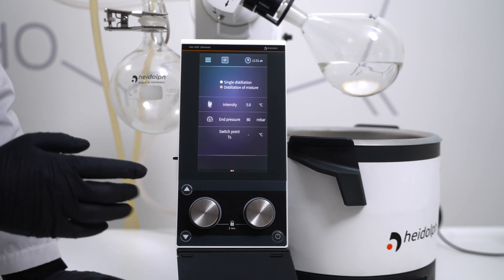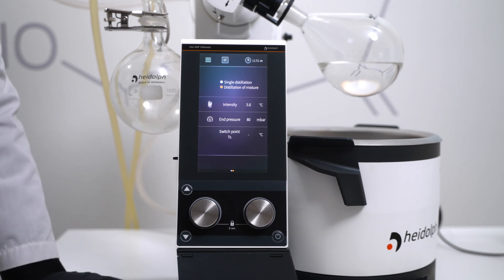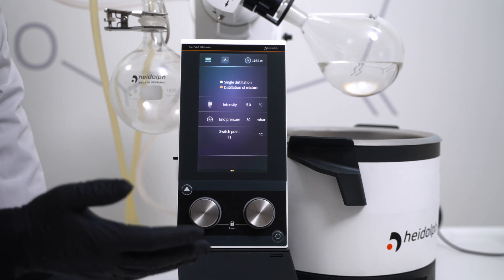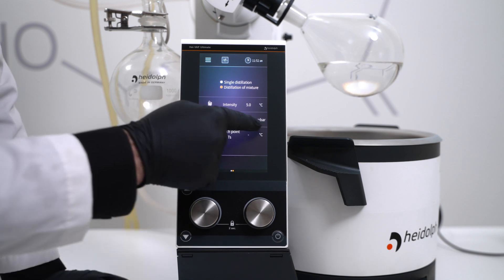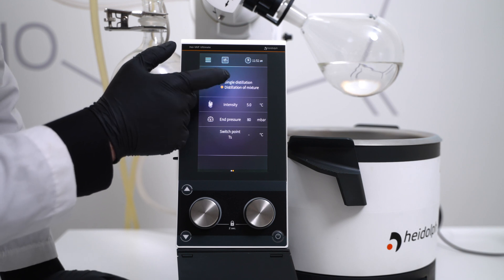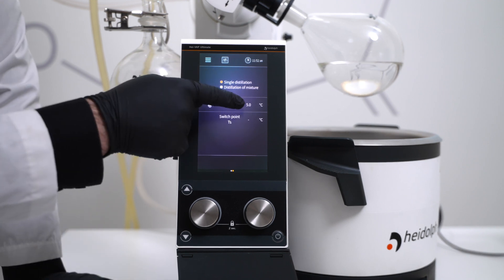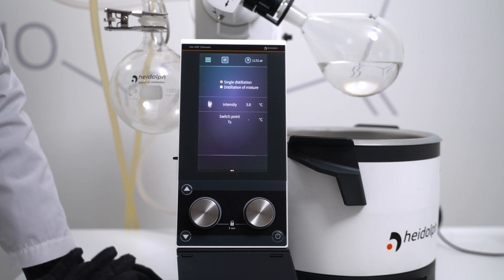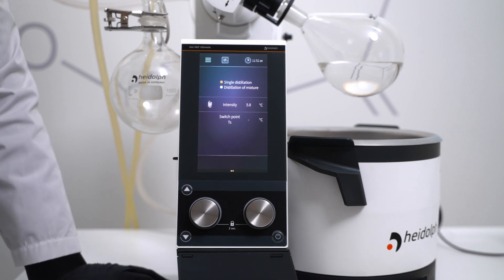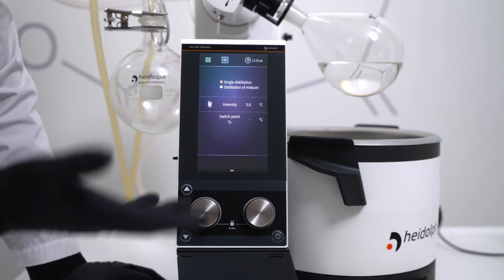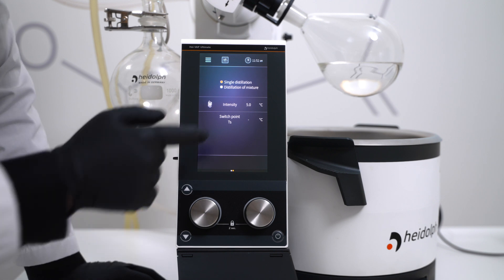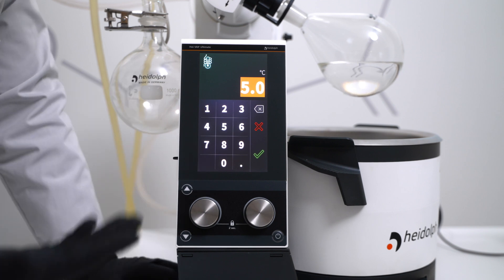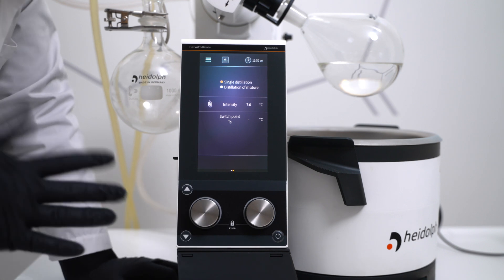There's only one big difference between the two, and that is an end pressure. With single distillation, after it is finished evaporating your first solvent, it will turn off the process. With distillation of mixture, it will continually evaporate different solvents until you hit an end pressure. In our case, we're going to be doing a single distillation. Lastly, there is the intensity point I mentioned earlier. You can put in a value between 1 degree and 10 degrees — 10 being a very quick evaporation, 1 being a slower, more precise evaporation. I usually start at around 7 and adjust to fully optimize.